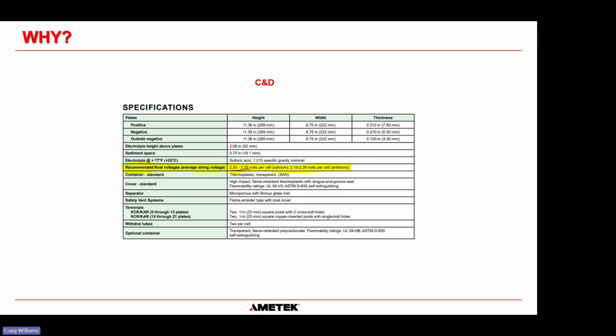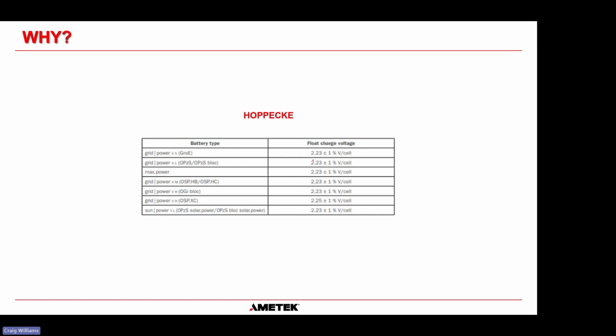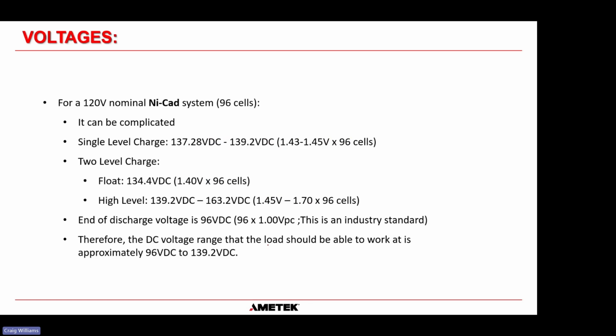C and D, once again, say the float voltage should be 2.2 to 2.25 for calcium and 2.15 to 2.28 for antimony. So we're not making these numbers up. The battery manufacturer is what is driving the float voltage for the battery. It's not some made up number that you should stick by. Most people will say 2.25 volts per cell, but that's not correct. You do have to check the specifics of the battery that you're charging. And for Hoppecke, they're saying it's 2.23 volts per cell, except for this one here, which says it's 2.25 volts per cell. So you can see it's very different for each technology that's out there.